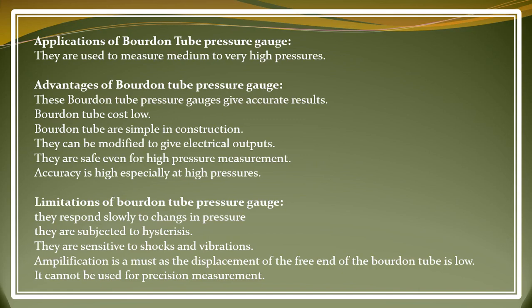The next is that accuracy is high, especially at high pressure. So its accuracy is high; this is the main advantage of the Bourdon tube. Limitation of Bourdon tubes: they respond slowly to change in pressure. As we can see, when we apply the pressure on the Bourdon tube, it mechanically rotates the sector and pinion and all the system, so it is slow in response. So the response time is slow.